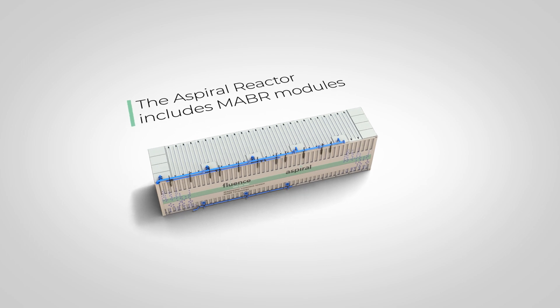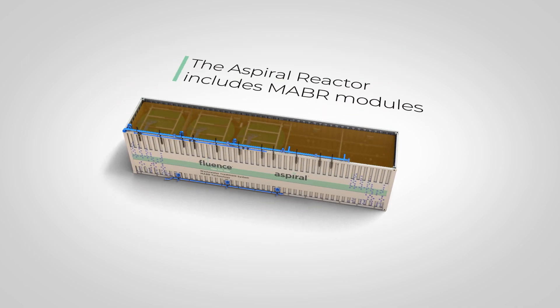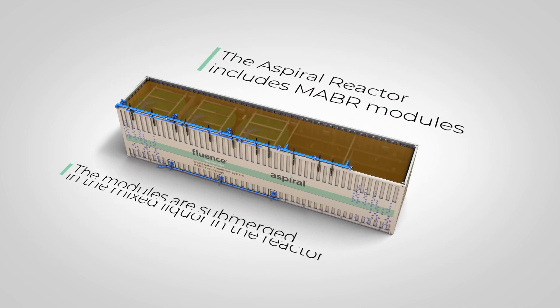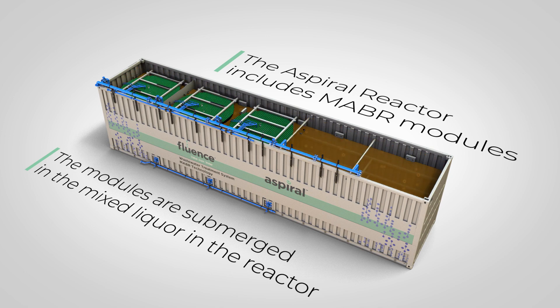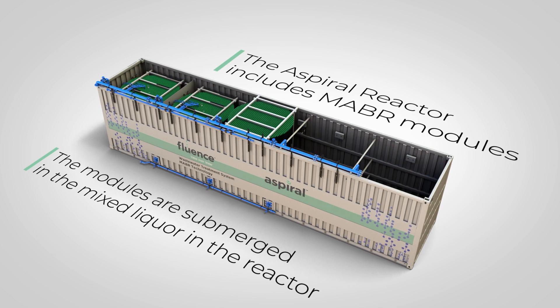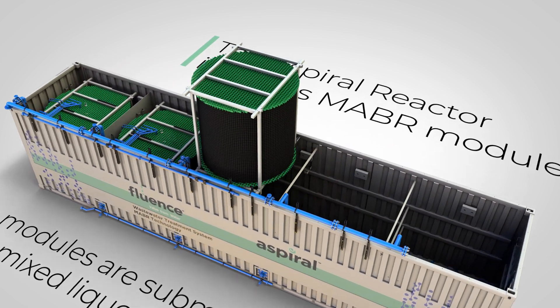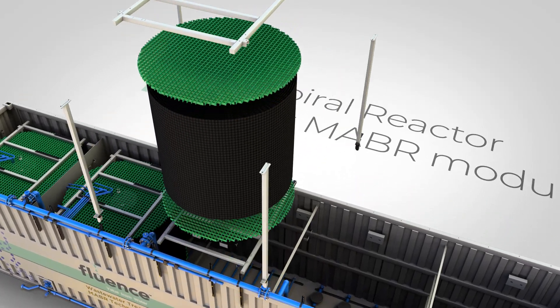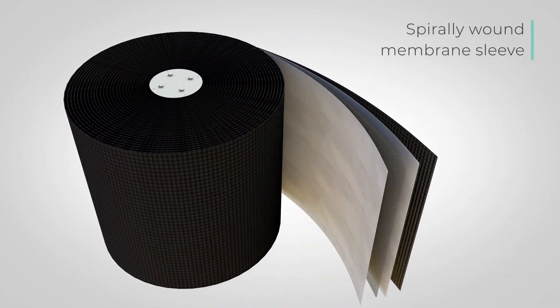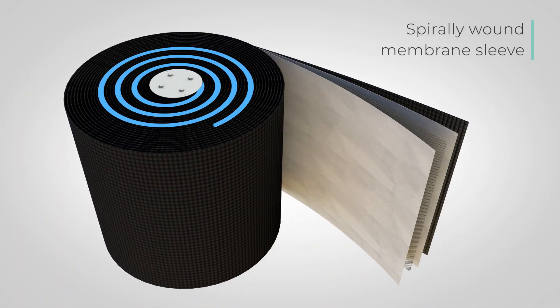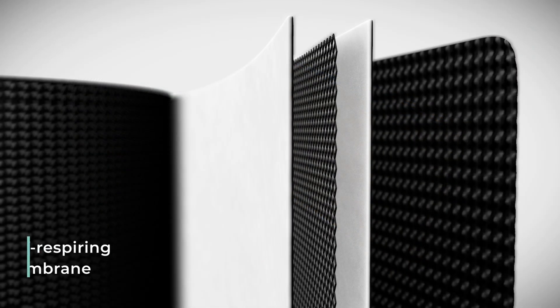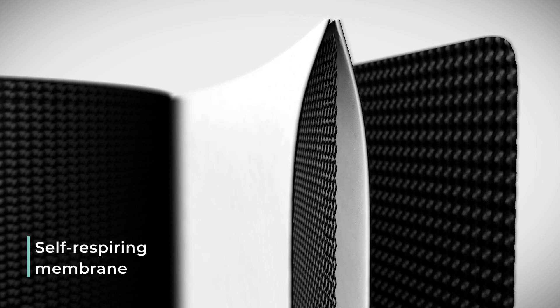An Aspiral reactor is comprised in part of MABR modules made of spirally-wound, flat-sheet self-respiring membranes. Each MABR module is made of a long membrane sleeve with an internal air spacer and an external water spacer. Low-pressure air is continuously blown through the sleeve, saving much of the energy consumed in higher-pressure conventional aeration.